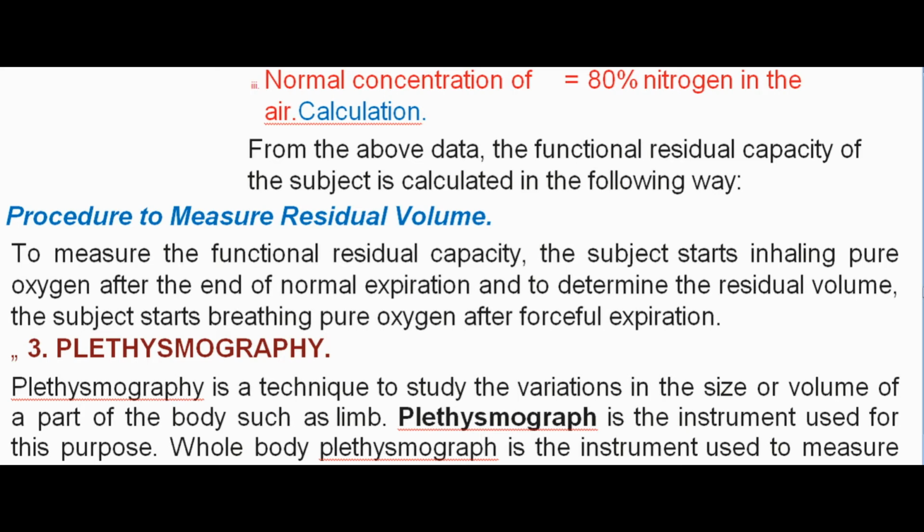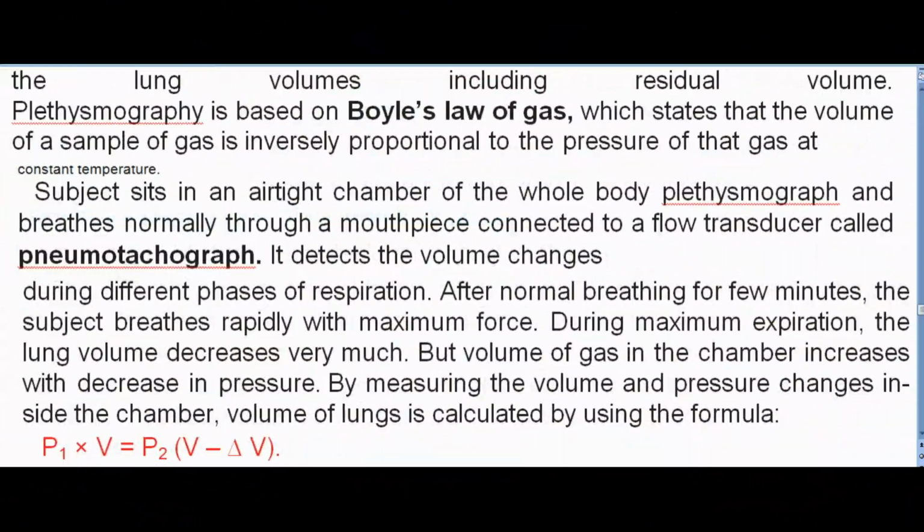Plethysmograph is the instrument used for this purpose. Whole body plethysmograph is the instrument used to measure the lung volumes, including residual volume. Plethysmography is based on Boyle's law of gas, which states that the volume of a sample of gas is inversely proportional to the pressure of that gas at constant temperature.